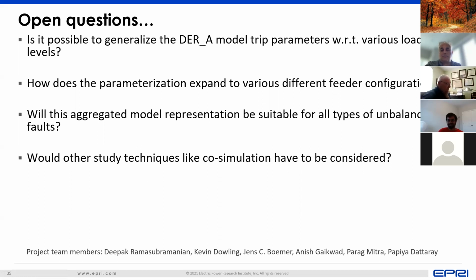It seems that the benefit of DER spread across multiple distribution circuits is a blessing for the grid. However, DER spread across a large number of distribution circuits is a curse for the grid because it is impacted by so many things that the grid operators have no control over, notably weather. When a cloud system moves across a distribution area, which is geographic, the load drop occurs across that area. So it's hard to say it's a single event.